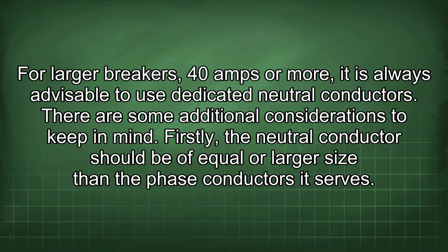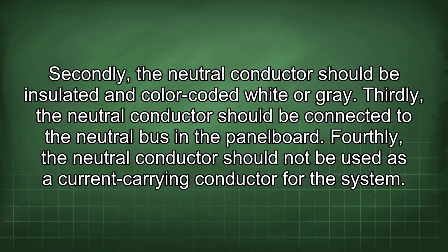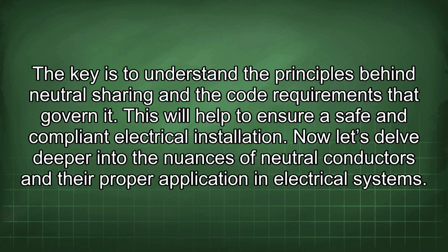There are some additional considerations to keep in mind. Firstly, the neutral conductor should be of equal or larger size than the phase conductors it serves. Secondly, the neutral conductor should be insulated and color-coded white or gray. Thirdly, the neutral conductor should be connected to the neutral bus in the panel board. Fourthly, the neutral conductor should not be used as a current-carrying conductor for the system. The key is to understand the principles behind neutral sharing and the code requirements that govern it. This will help to ensure a safe and compliant electrical installation.